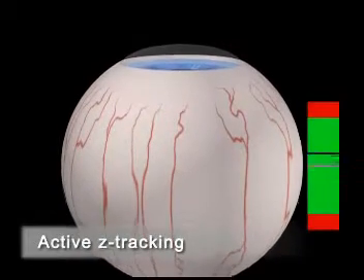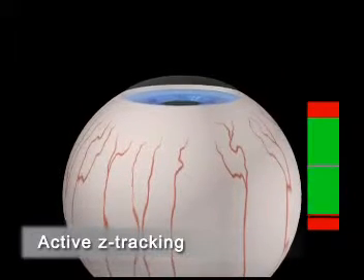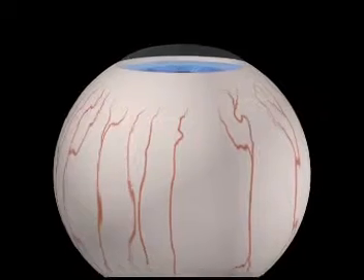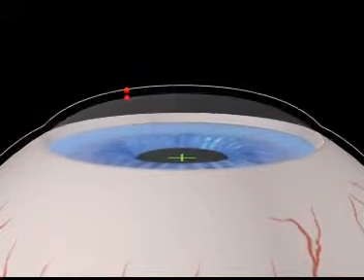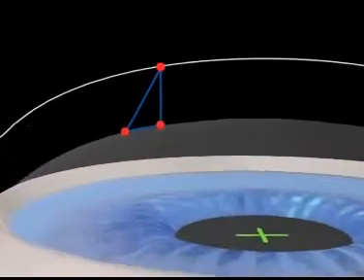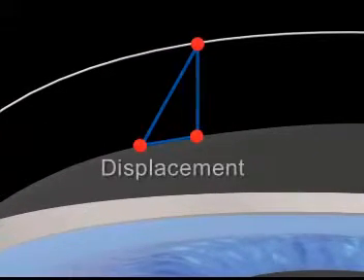With the Schwind Amaris, for the very first time, eye movements along the Z axis are compensated with active Z tracking. Ablative spots are repositioned to actively compensate for the lateral deviations induced by eye movements along the Z axis.